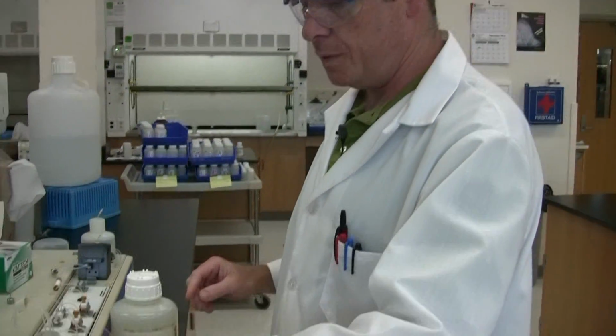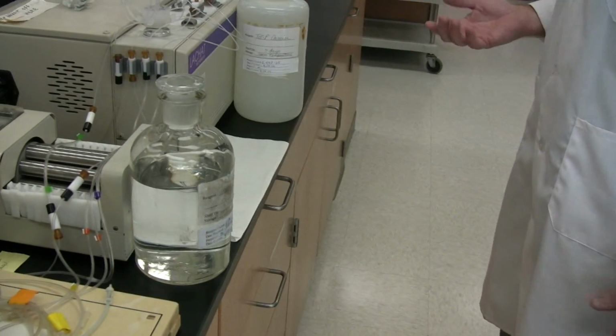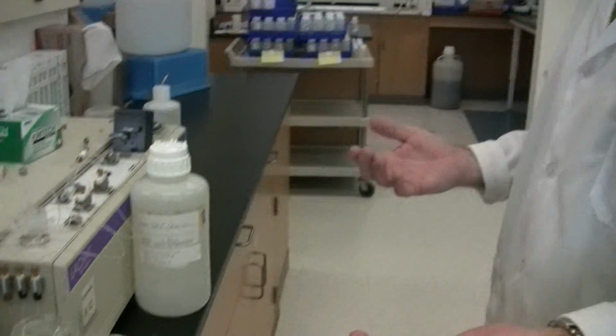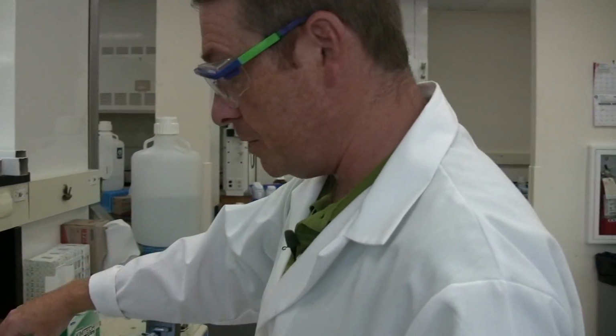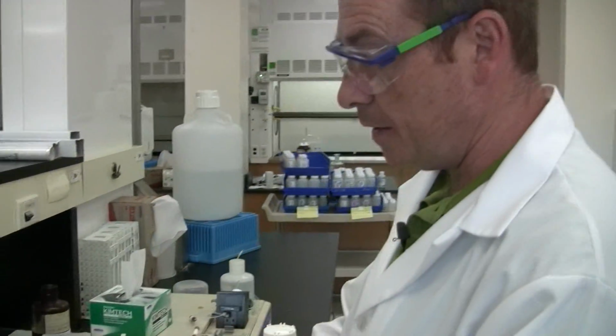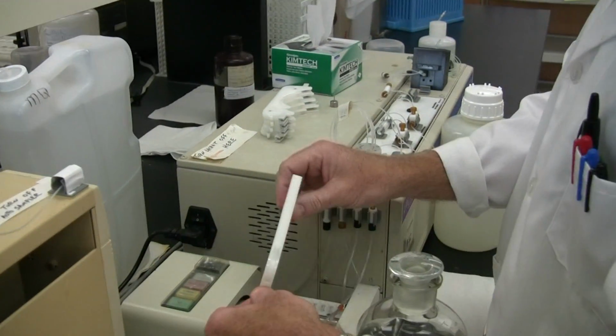A couple of these reagents we degas with helium. If you can imagine, if you shake a can of pop to get rid of the fizz, basically bubbling the helium through, we're driving off any dissolved gases, and what that does is prevent bubbles from forming during the analysis, because bubbles cause problems in the instrument. I'm going to get the reagents going here just so the instrument's ready to go.